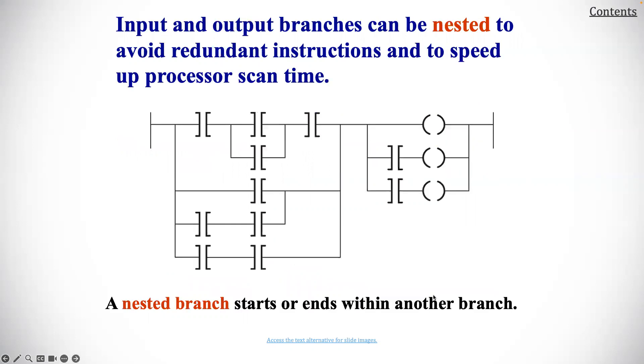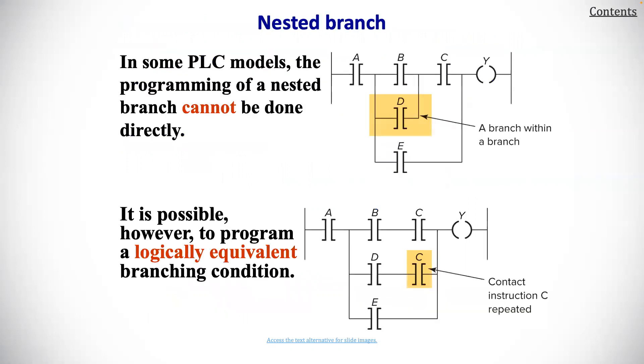Input and output branches can be nested to avoid redundant instructions and to speed up processor scan time. A nested branch starts or ends within another branch. For nested branches, in some PLC models, the programming of a nested branch cannot be done directly. It is possible, however, to program a logically equivalent branching condition.